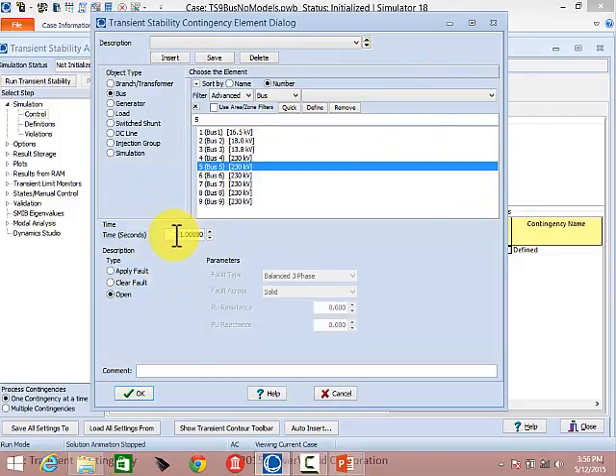Your time input is very important: when in your simulation do you want to apply this action? As for why everything starts at one second — it can start whenever you want. Usually, cases are run for one or two seconds to show that they are flat. If they're not flat, you'll see growing oscillations, indicating either numerical instability or bad data.